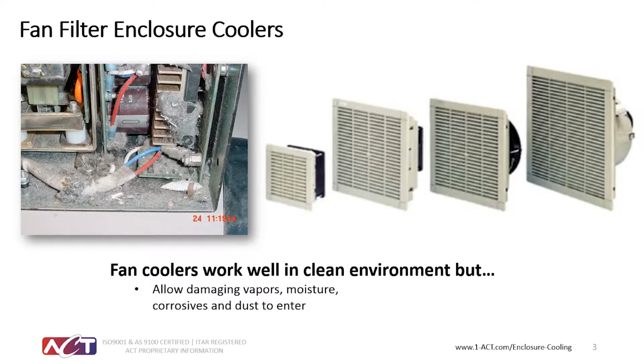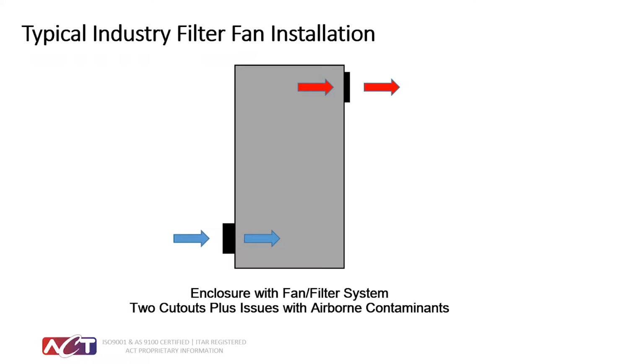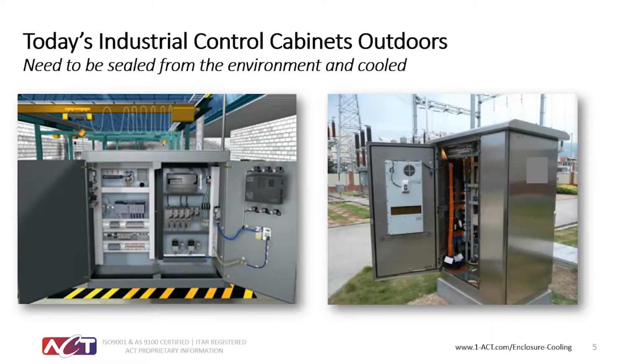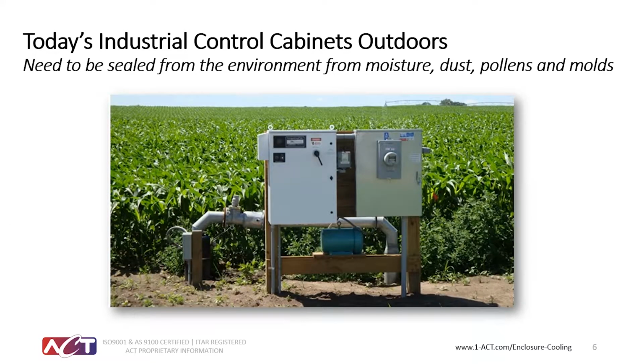It's easy to visualize the damage caused by corrosive chemicals such as chlorine, ammonia, or hydrogen peroxide cleaning agents that may collect or even come in contact with the inside or outside of the unsealed enclosure. Structural damage and component failure can occur. That's for indoor applications. Outdoor applications present their own challenges. Enclosures and their internal components can be damaged by salt spray, agricultural dust, and molds that can electrically bridge circuits and cause systemic electrical failure.